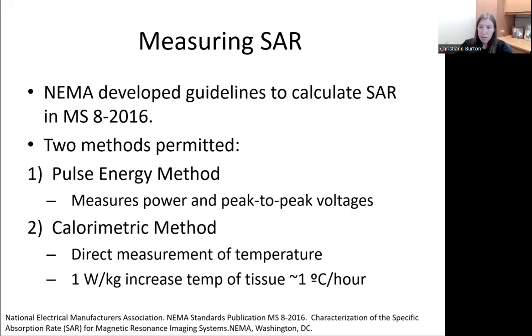The National Electrical Manufacturers Association, or NEMA, has developed guidelines for measuring SAR generated by equipment using phantoms, incorporated in their standard MS-8 2016. These procedures are used by manufacturers to calculate SAR for their MRI systems. There are 2 basic methods that are permitted. The first is the pulse energy method. This method is a little complicated. Basically, a directional coupler is used to measure forward and reflective power, together with an oscilloscope to measure peak-to-peak voltages. Coil losses are assessed using a non-loading phantom, while a loading phantom is used to measure sample losses.